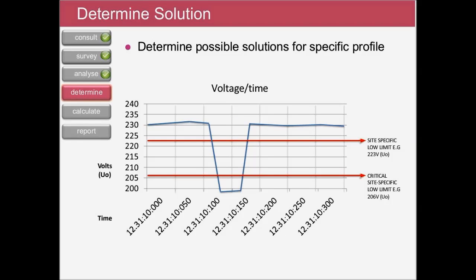So in our example, we can see a representation of the voltage dip. This was caused by an inrush current on the LV network. As the duration of the voltage dip exceeds 40 milliseconds, this would decrease the stability of the load and, of course, therefore increase the risk of failures. It's therefore important to quantify this element, and by programming alarms within the power quality analyzer, we can identify the most appropriate solution, including, if necessary, hardware capable of mitigating the risks associated with these conditions.